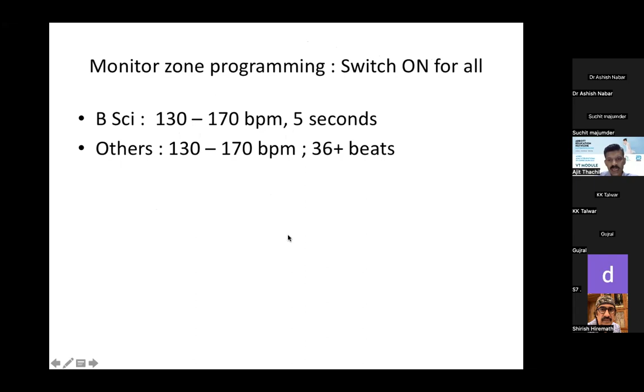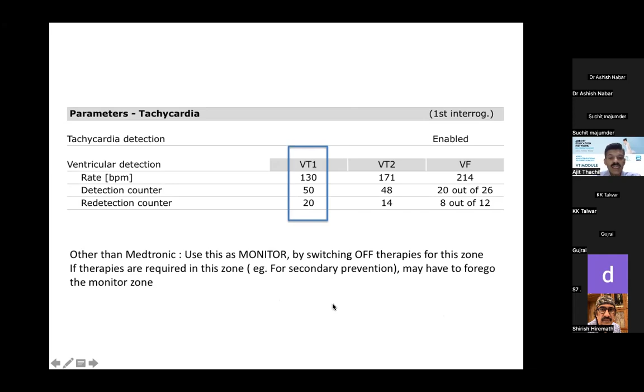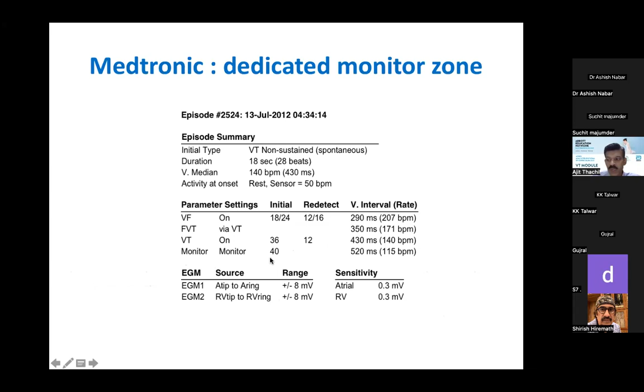Now, other than Medtronic, other manufacturers don't have a genuine monitor zone. So we like to use the VT1 zone as a monitor zone by switching off therapies in this zone. But if therapies are required in this zone, for example, you want to treat a ventricular tachycardia at 150, then you will have to turn on therapies in this zone and forego the monitor zone. Whereas in Medtronic, there is a dedicated monitor zone. You can turn on the monitor.